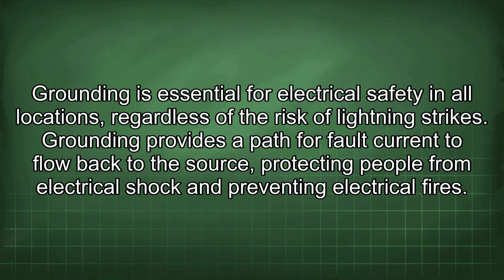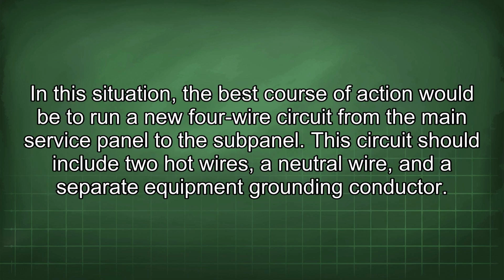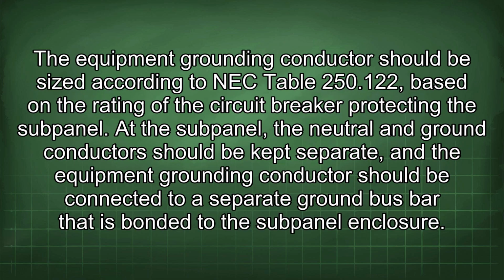In this situation, the best course of action would be to run a new 4-wire circuit from the main service panel to the subpanel. This circuit should include 2 hot wires, a neutral wire, and a separate equipment grounding conductor. The equipment grounding conductor should be sized according to NEC Table 250.122, based on the rating of the circuit breaker protecting the subpanel. At the subpanel, the neutral and ground conductors should be kept separate, and the equipment grounding conductor should be connected to a separate ground bus bar that is bonded to the subpanel enclosure.